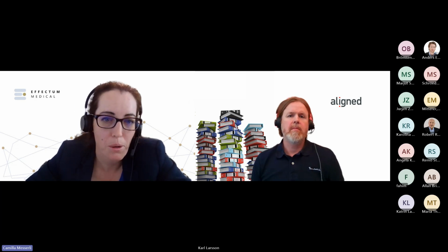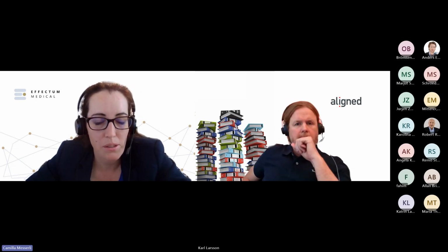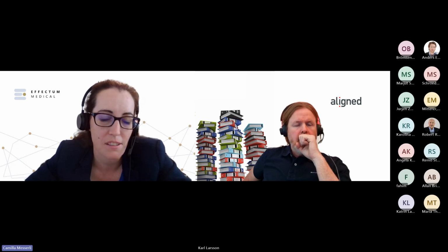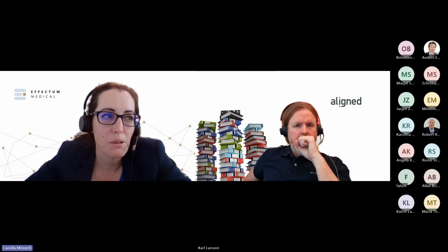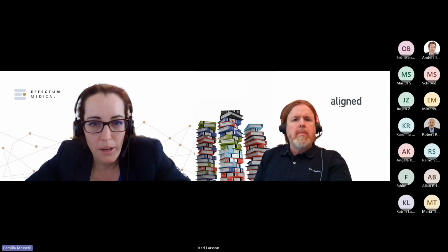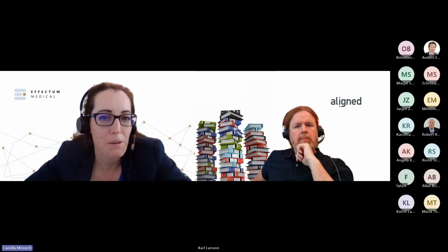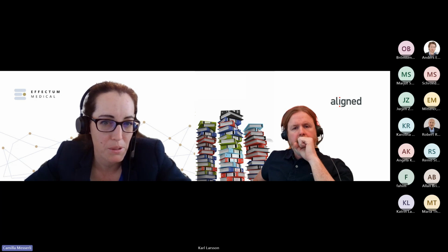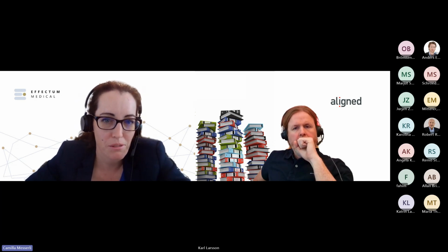Now, if it's just twice the feedback that you got, then you just say, well, actually, it's not very often. We have 20,000 products on the market. There's no need to do anything. So you have the power to say no need for further actions at this time. That's always a good statement, at this time. And if you see something that you would just dismiss if you see it once, but now you've received 100 times similar feedback, then maybe that's a problem. Then you need a very good justification if you really want to say there's no need to do anything, because your argumentation is being taken away by 100 feedbacks out there.